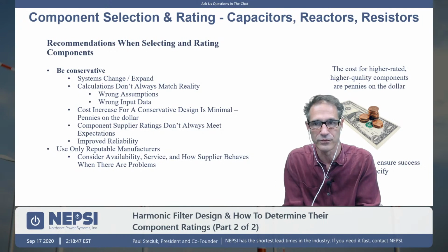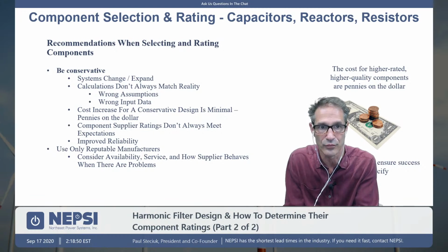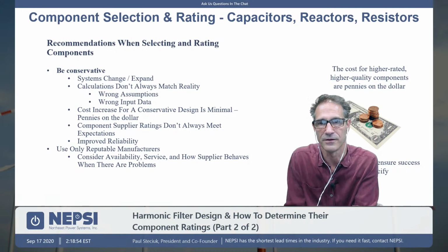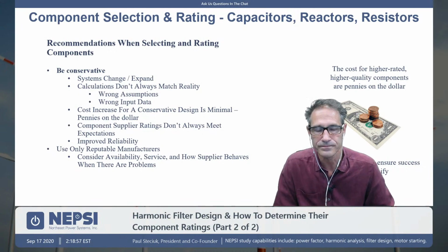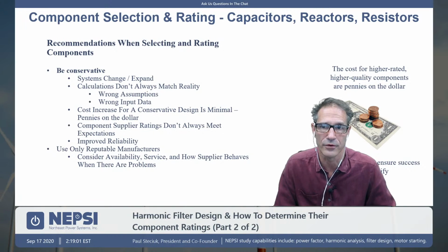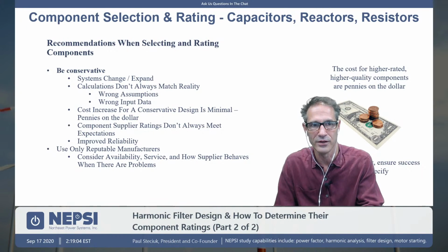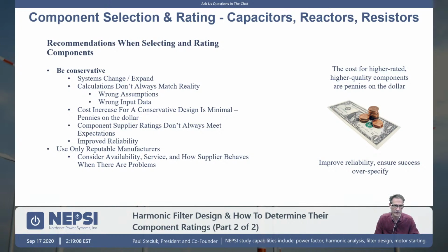If you add more harmonic current sources to a system that has a marginally rated filter, it's going to potentially get hot and burn up. So the cost to increase component ratings is pennies on the dollar. It really is, and I kind of show that over here. You already have a reactor that's custom made. You have potentially capacitors that are custom made. You're buying a whole harmonic filter system that is custom made. So adding additional ratings to the reactors and to the capacitors is really going to cost you pennies on the dollar. So we highly recommend that you put a significant amount of harmonic current rating and harmonic voltage rating on the components. We're going to talk about that as we move along in this presentation.